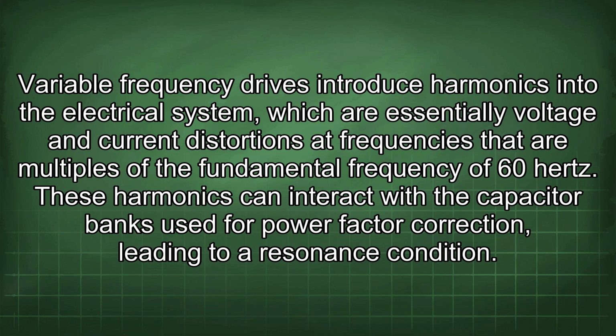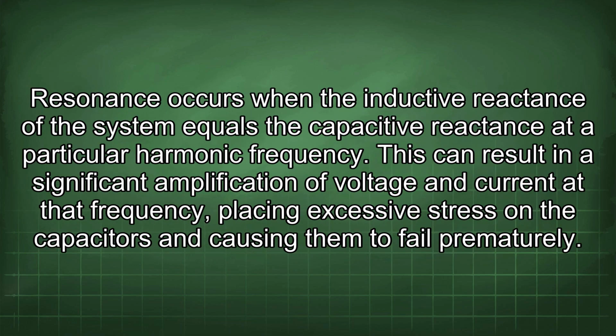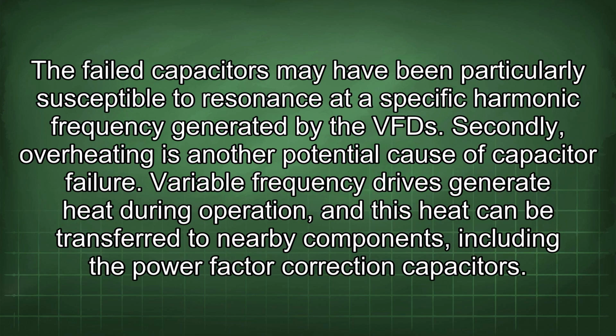These harmonics can interact with the capacitor banks used for power factor correction, leading to a resonance condition. Resonance occurs when the inductive reactance of the system equals the capacitive reactance at a particular harmonic frequency. This can result in a significant amplification of voltage and current at that frequency, placing excessive stress on the capacitors and causing them to fail prematurely. The failed capacitors may have been particularly susceptible to resonance at a specific harmonic frequency generated by the VFD.